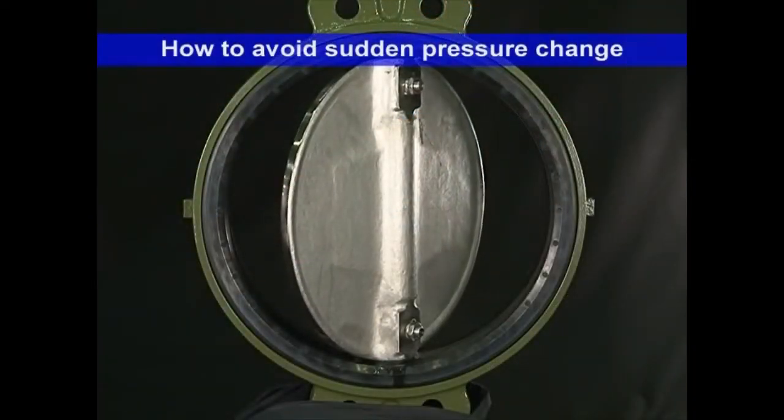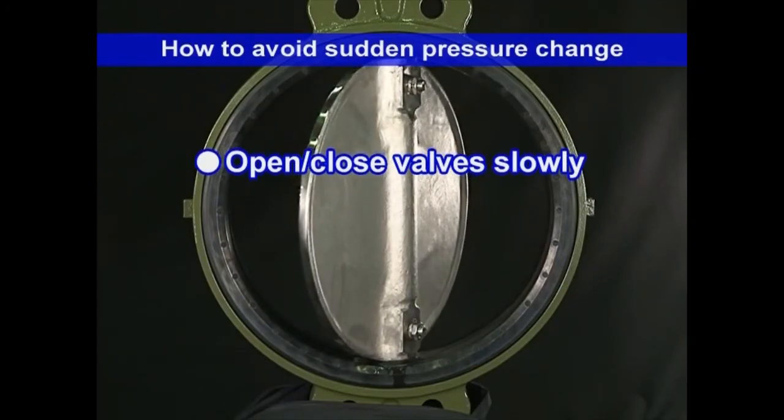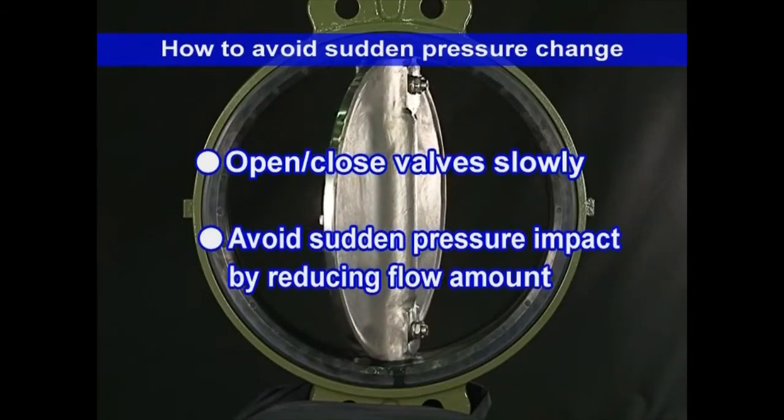The key to avoiding such troubles is to open or close valves slowly. It's also important to reduce the amount of flow in advance so that sudden pressure impact will not be placed on the pipeline.